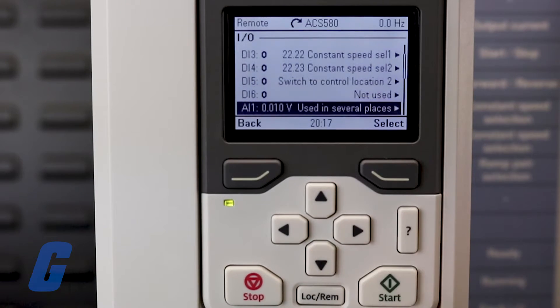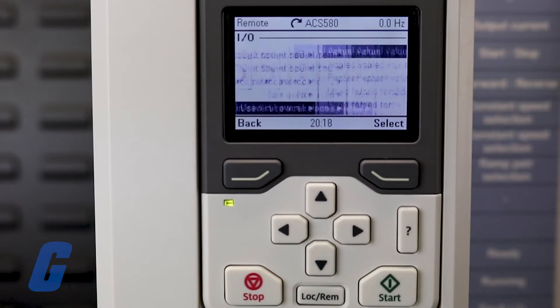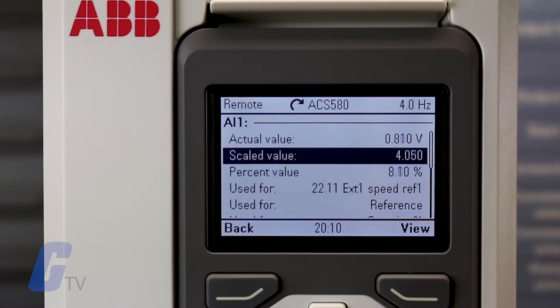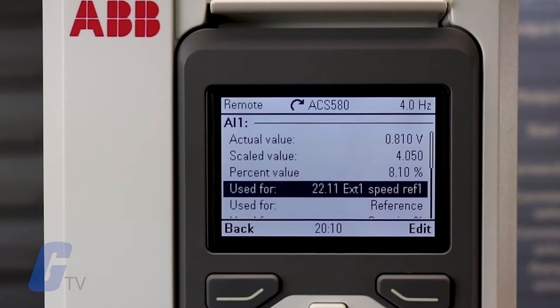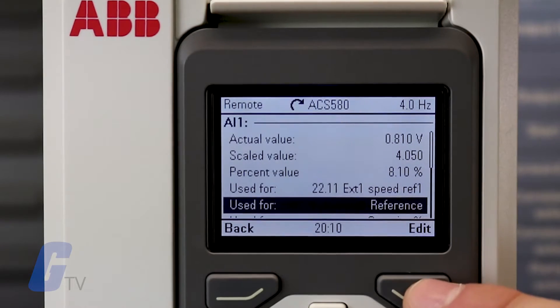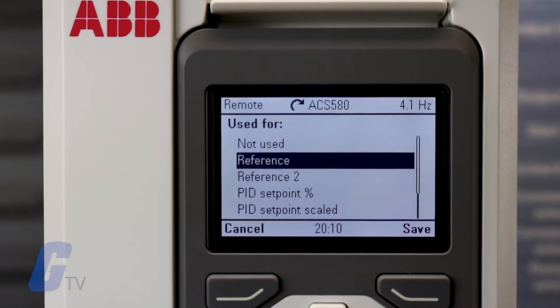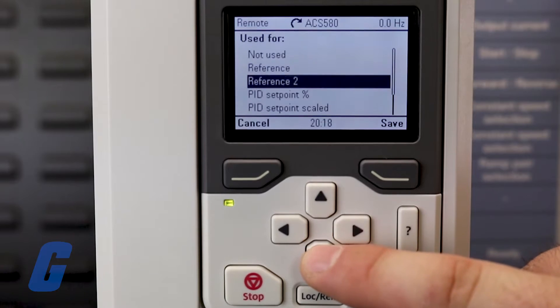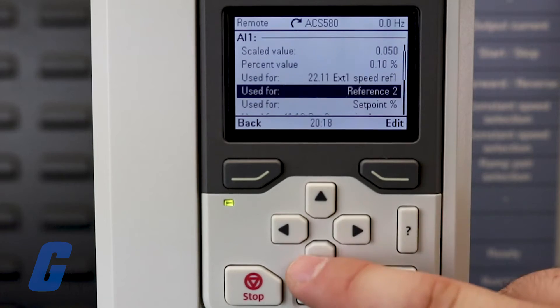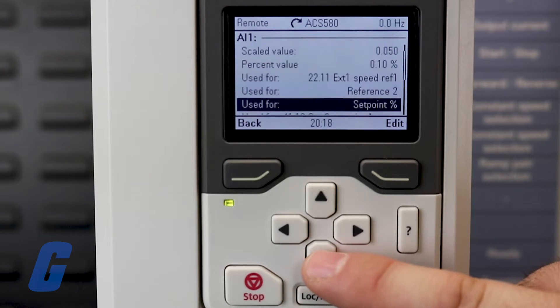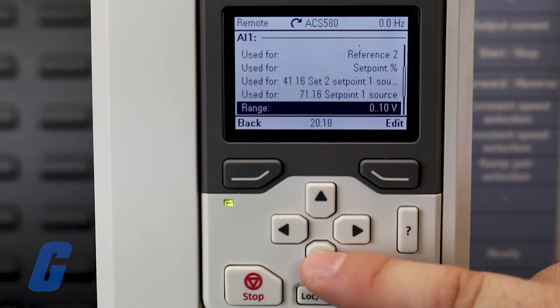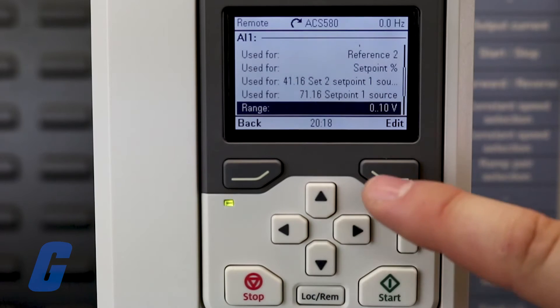Depending on the terminal, different signals have been pre-selected for use and range limits. If the range unit is changed from volts to milliamps, the hardware switch needs to be changed to the respective unit as well.